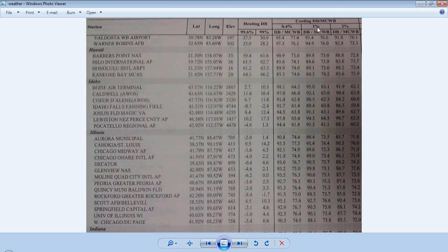And then for the cooling side, the correct column that you would normally use for dry bulb and cooling would be the 1% column, meaning that 99% of the summer hours I'm covered. So for Aurora, 88 degrees. For Chicago O'Hare, 89 degrees. For Chicago Midway, 90 degrees. Right? So you can see some of these ones, St. Louis, 91. So it's basically pulling 89 degrees in that report because that's what it's getting for Aurora there.